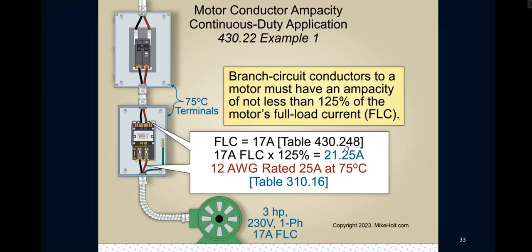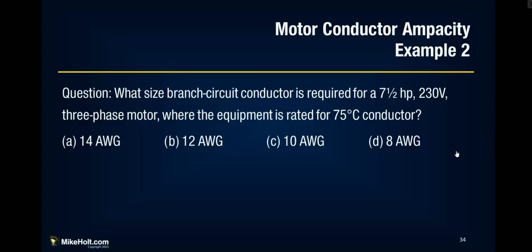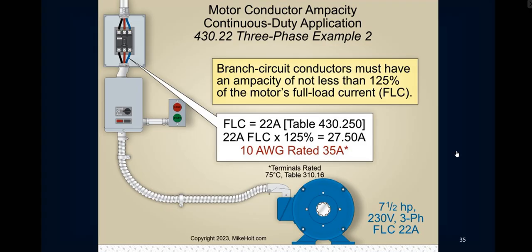So 17 amps, which comes from 430.248, FLC times 125% is 21.25. Number 12 AWG, rated at 25 amps at the 75 degrees Celsius column, would be your correct conductor size. What size branch circuit conductor is required for a 7.5 horsepower 230-volt three-phase motor, 75 degrees Celsius conductors?